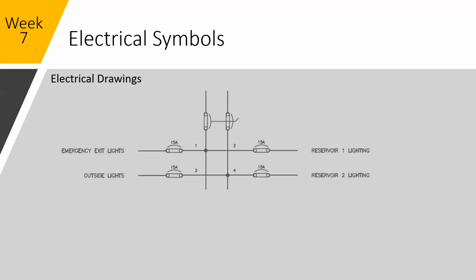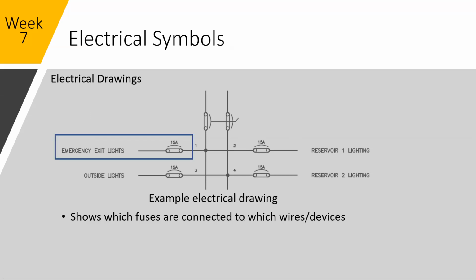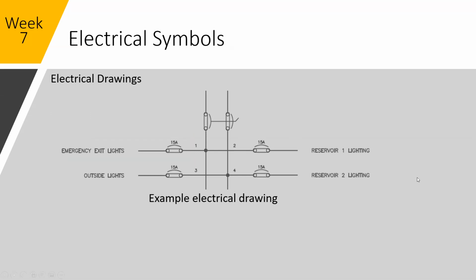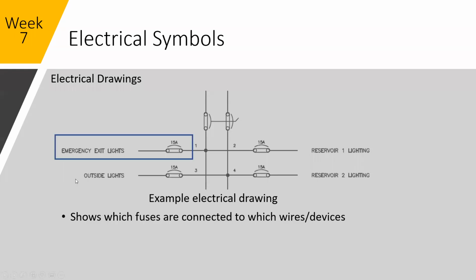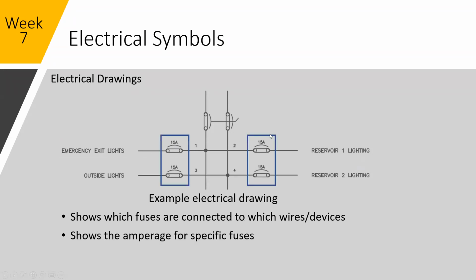a lighting schedule or a fuse panel, breaker panel. What you have here at the top are, this section is showing that you have emergency lighting connected to fusing. There's a 15 amp fuse connected to these emergency lights. On this side, you've got 15 amp fuses connecting to these reservoir lights. They'll show the amperage and again, the devices that they're being supplied to.